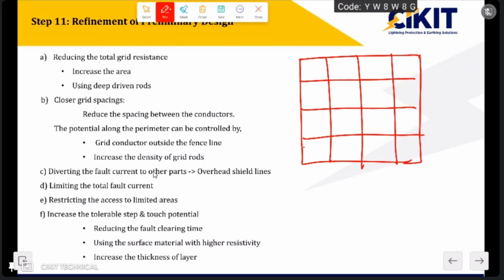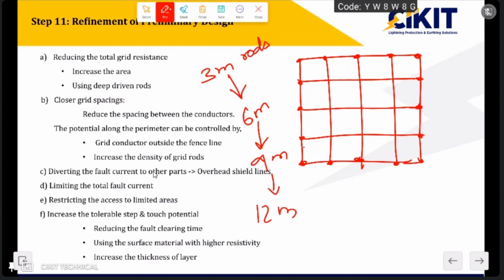Initially I can go for earth electrodes at random places. Then I can check what the values are. If the value is still not achieved, then I can increase the number of earth electrodes. If initially it is 4, then I can increase from 4 to 8. Even if increasing the earth electrode numbers does not achieve this value, then I can increase the length of the earth electrode. Initially if I'm going for 3-meter rods, I can increase the length from 3 meter to 6 meter, or 6 meter to 9 meter, or 10 meters. Similarly, I can increase the length of the rods to achieve lower step and touch voltage values.